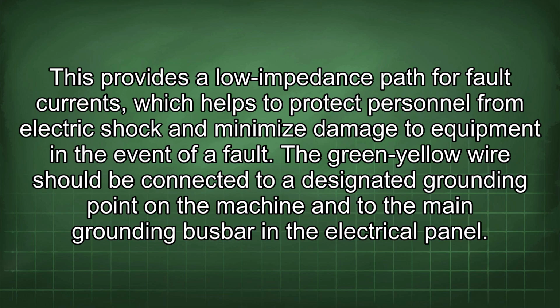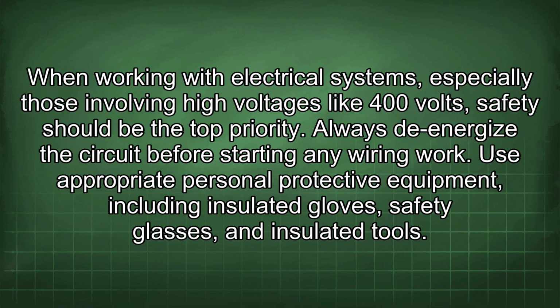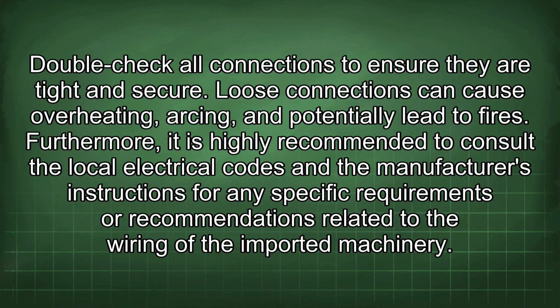The green-yellow wire should be connected to a designated grounding point on the machine and to the main grounding busbar in the electrical panel. When working with electrical systems, especially those involving high voltages like 400V, safety should be the top priority. Always de-energize the circuit before starting any wiring work. Use appropriate personal protective equipment, including insulated gloves, safety glasses, and insulated tools. Double-check all connections to ensure they are tight and secure. Loose connections can cause overheating, arcing, and potentially lead to fires.